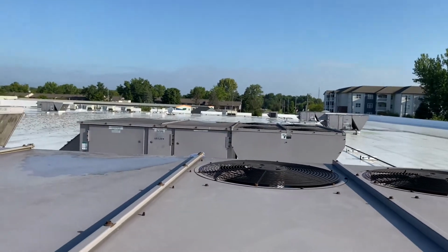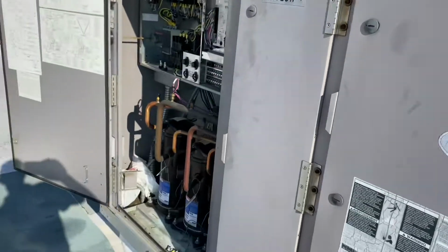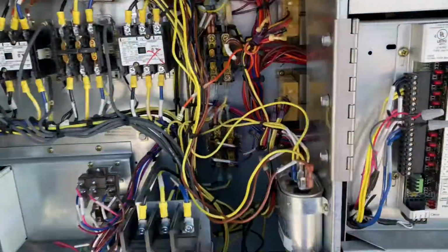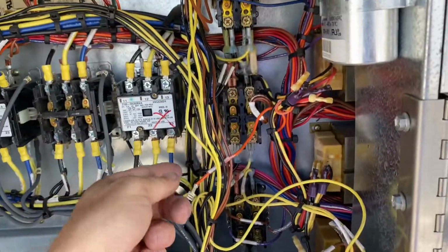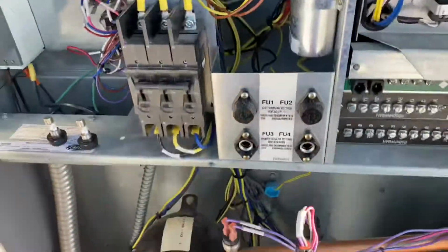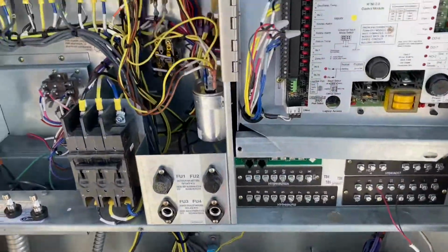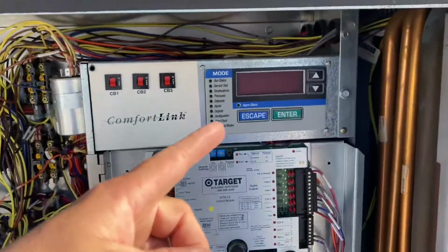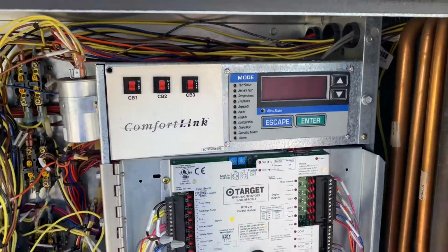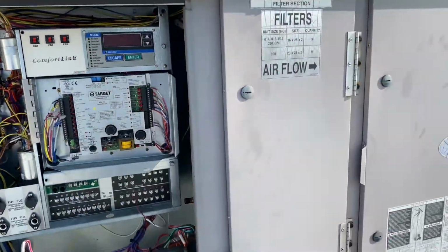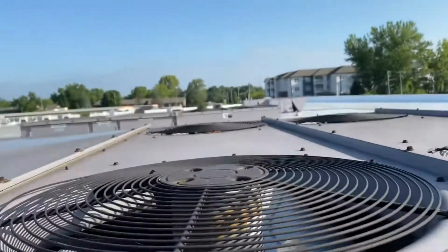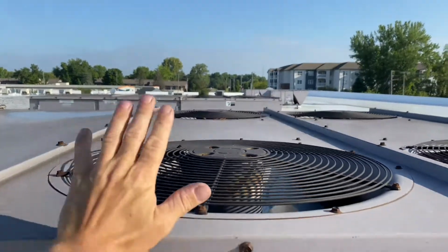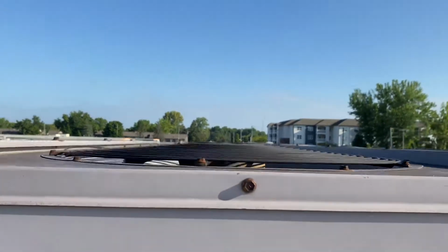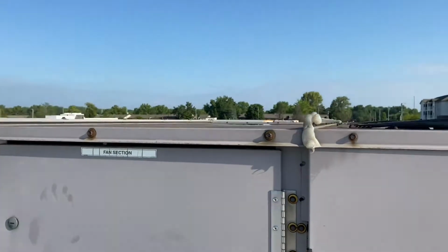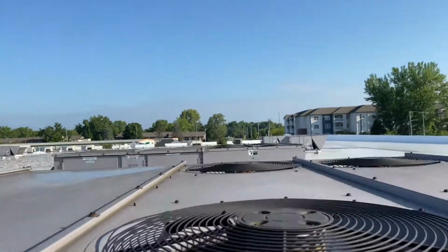I then unlanded the wires for that contactor, which is contactor 2. Like I said, unlanded 24-volt power for that, replaced the fuse again, and then come back over here, put it in test mode to test outdoor fan 3, which contactor for outdoor fan 3, which is technically outdoor fan 4. And this one right here is 4. It ran fine. So what I'm gonna do now is I'm gonna shut it off, lock it out.